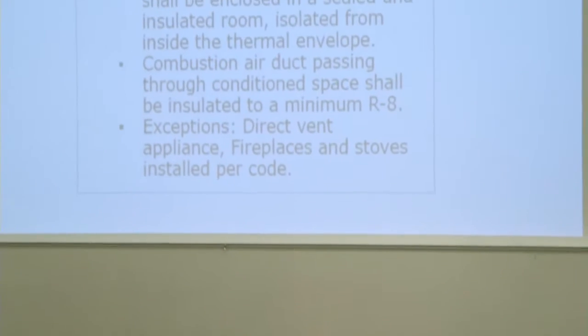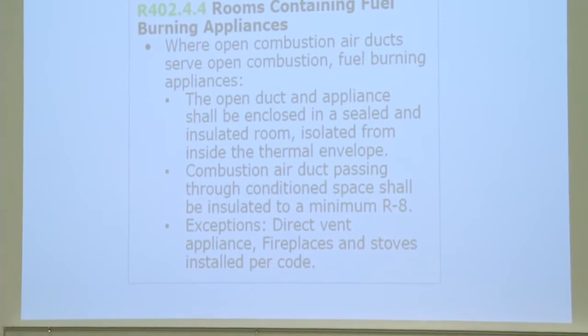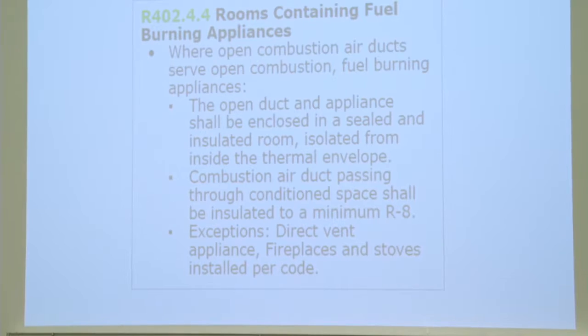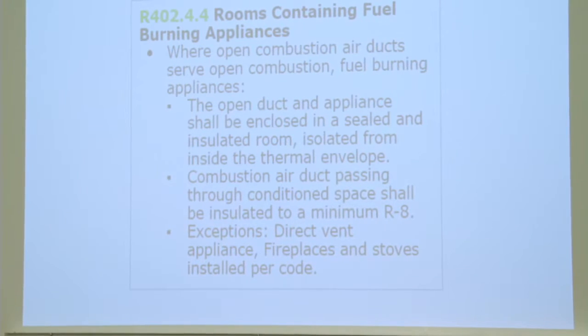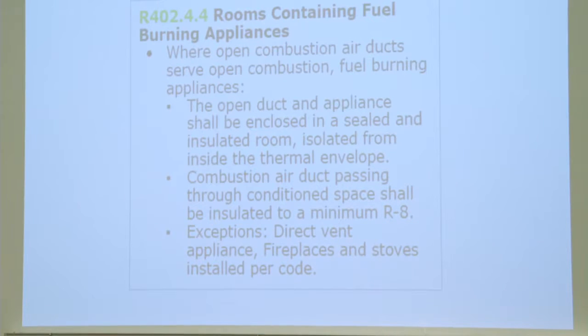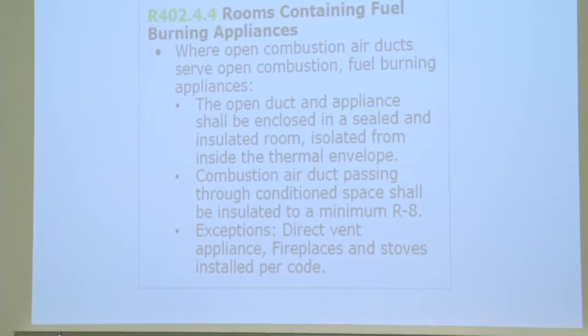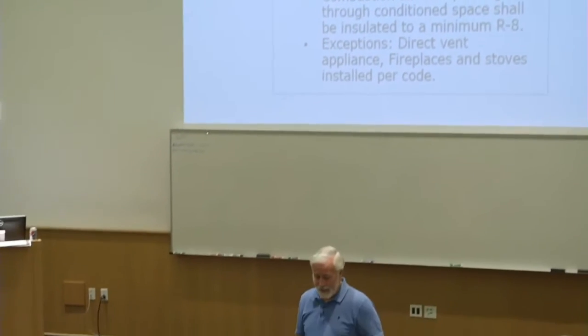And so what this code change says is basically if you have an open combustion appliance, and this can be a furnace or a water heater or both, in a house being served with an open combustion air duct, you have to enclose it in a room. The room has to be insulated to the level of a basement wall in your climate zone. And I'm the first to admit that that's probably the wrong number.